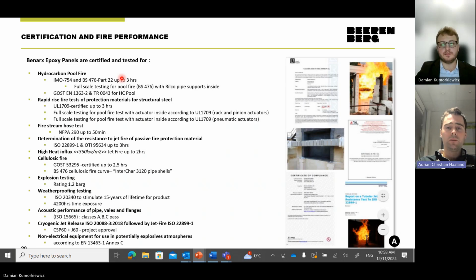The most common fire types that we encounter are hydrocarbon fire curves like BS 476 or UL 1709, and jet fire according to ISO 22899. We also see a lot of high heat flux jet fire, which now is finally coming out with a recognized ISO standard, which is very good for the industry. Explosion testing. In the later years, we've done more cryogenic testing, which I will come back to. And also some curiosities like fire water stream hose testing.